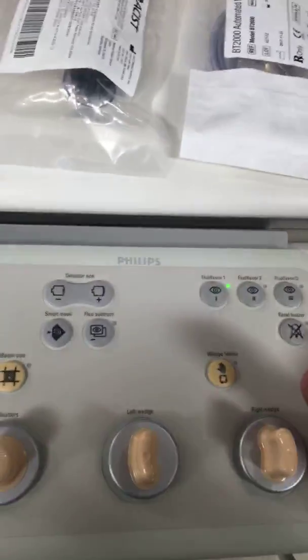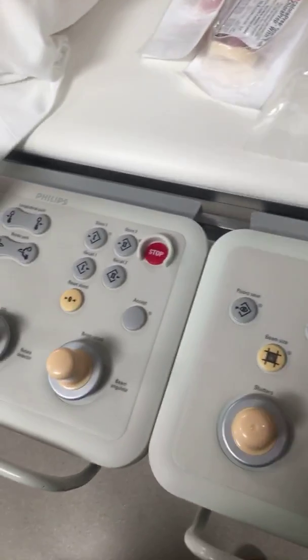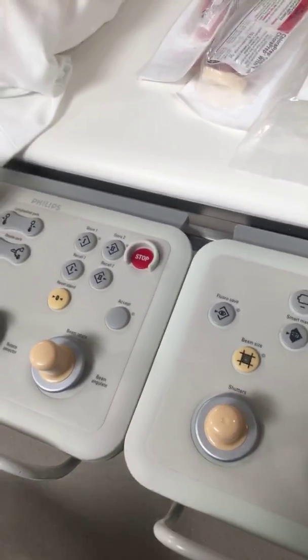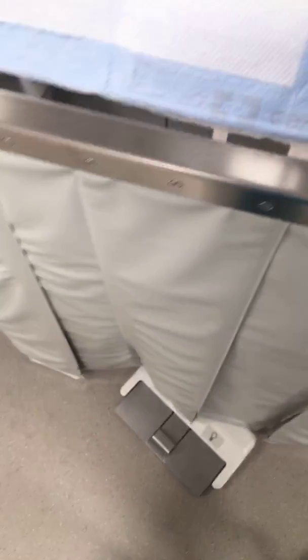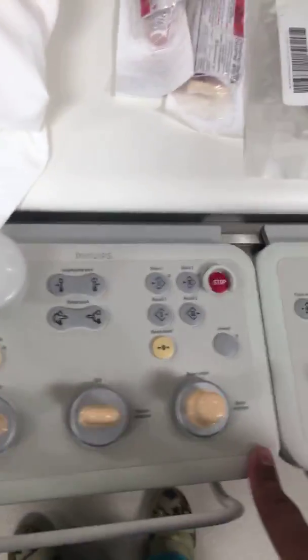Shutters. Pretty simplistic here. Fluoro save means that if you hit the fluoro button here, it'll X-ray, but it won't save. If you hit the cine button, it's a lot more radiation, a lot faster frames per second, and it saves automatically. So those are two different things. If you want to save radiation, you hit the fluoro button instead, and then you hit the fluoro save, and it'll put it into your archive and save it. But if you don't, it'll disappear. It'll never save it. You do always save radiation exposure, but you don't see the images.